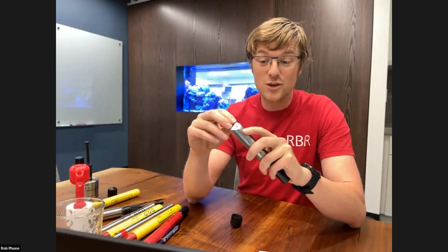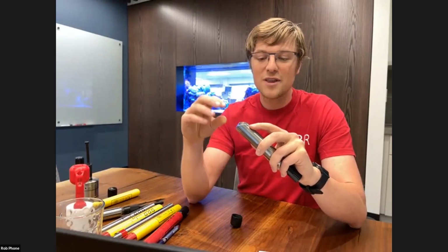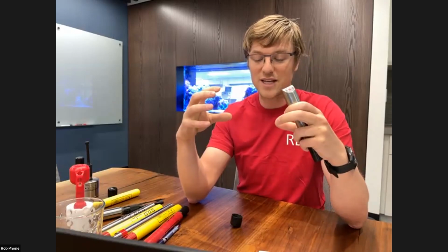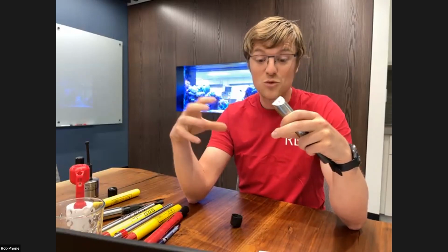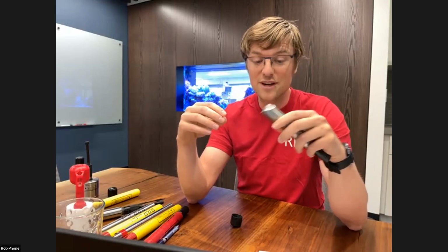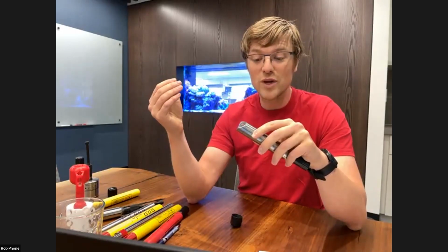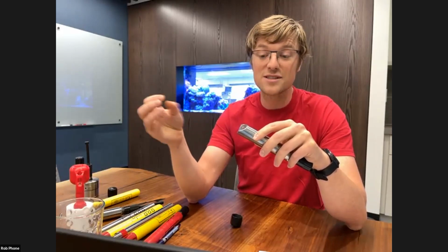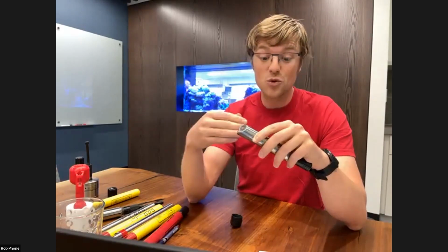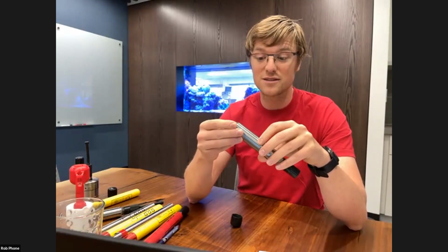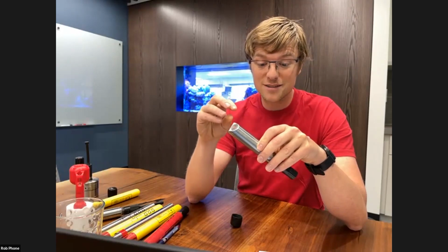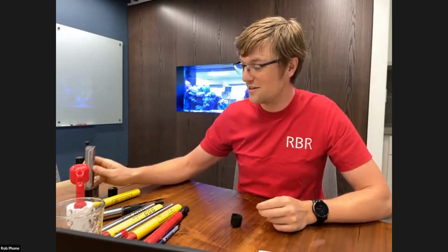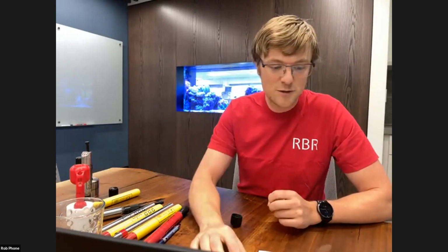This particular foil has quite a unique construction. The luminophore is packaged into the foil in a small molecular structure, which means we can put quite a few of the molecules in there. And to increase the signal, we embed a nanoparticle in there, which increases the scattering effect of the light, giving us quite a bit stronger signal than most other fast sensors. In fact, this one has a comparable sensitivity to that of the slow. So a very unique construction and a very good sensor.